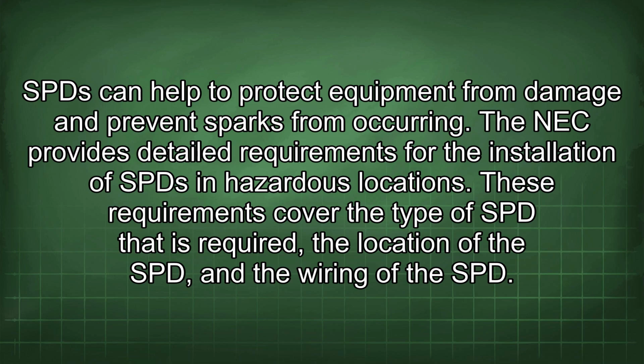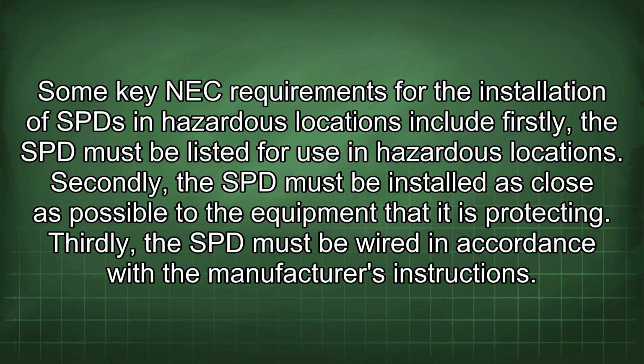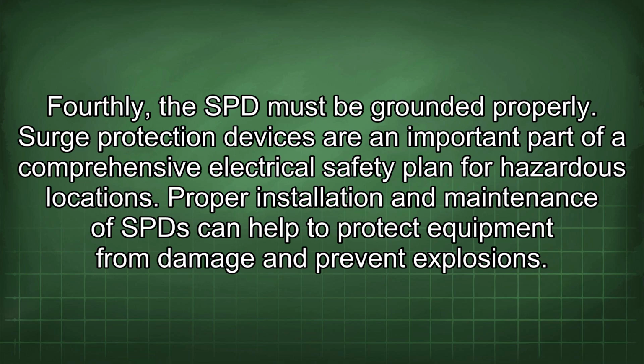The NEC provides detailed requirements for the installation of SPDs in hazardous locations. These requirements cover the type of SPD that is required, the location of the SPD, and the wiring of the SPD. Some key NEC requirements for the installation of SPDs in hazardous locations include: firstly, the SPD must be listed for use in hazardous locations. Secondly, the SPD must be installed as close as possible to the equipment that it is protecting. Thirdly, the SPD must be wired in accordance with the manufacturer's instructions. Fourthly, the SPD must be grounded properly.